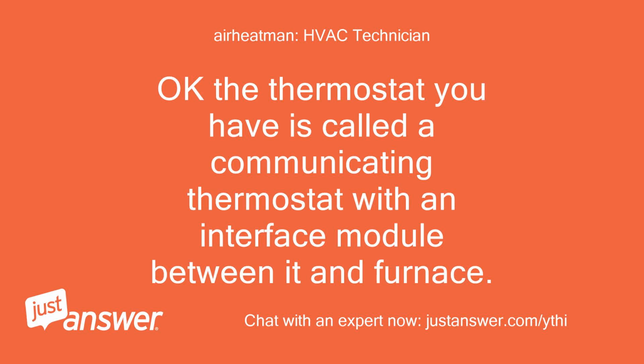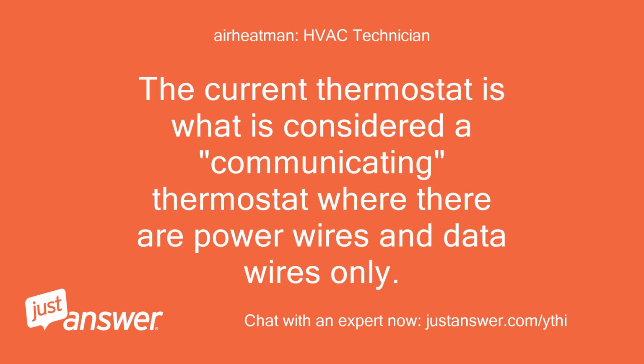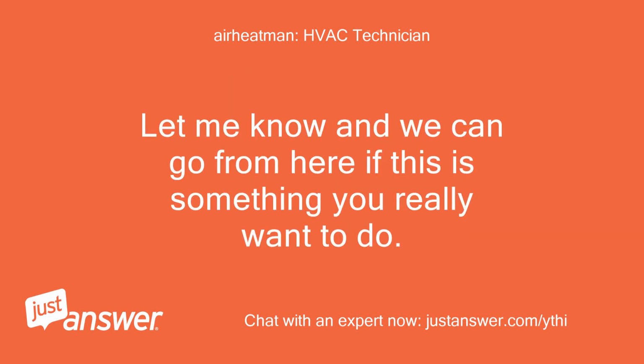Okay, the thermostat you have is called a communicating thermostat with an interface module between it and the furnace. They are two totally different types of thermostats. The current thermostat is what is considered a communicating thermostat, where there are power wires and data wires only. The Nest is a conventional thermostat where each letter terminal controls a specific thing. R is 24V power, G controls fan, W controls heat, Y controls compressor contactor, etc. If you can look inside your equipment, furnace or air handler and outdoor unit, and see if we have these extra R, G, Y, W, C, etc. terminals, then we can convert to a conventional thermostat, but you will lose some of the efficiency and functions of the communicating system. Let me know and we can go from here if this is something you really want to do.